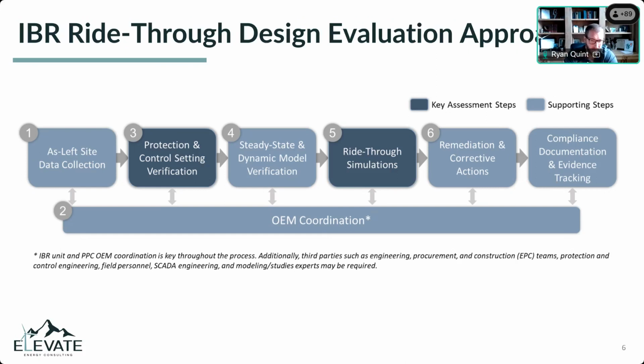Then we can look at what passes, what fails from a standard and requirements perspective, and what changes or corrective actions need to be put into place. Maybe it's moving the balance of plant relay settings, modifying control parameters, tuning controls, or adjusting IBR unit capability settings. All of that gets evaluated, often with an iterative approach going back to certain steps, updating, and driving forward a design evaluation that complies with the standard, or where possible, exemptions may be needed for previously in-service equipment.